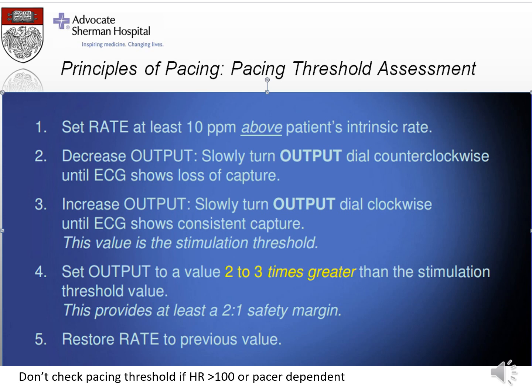What you will next do is you'll slowly decrease the output. So you'll go down on the MA until you lose the capture and you're no longer 100% paced and the patient has their own intrinsic rhythm. Then what you do is you start slowly increasing the MA or your output until you get that 100% paced again. That will be your threshold.